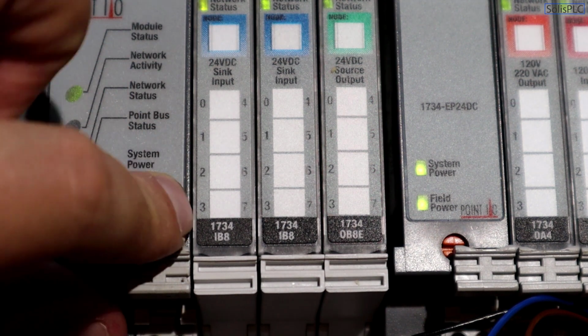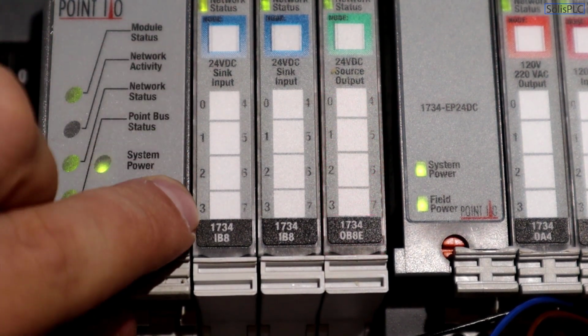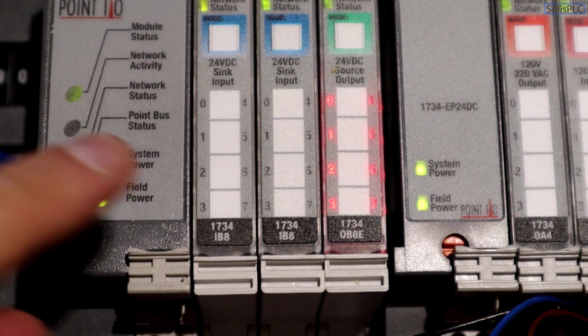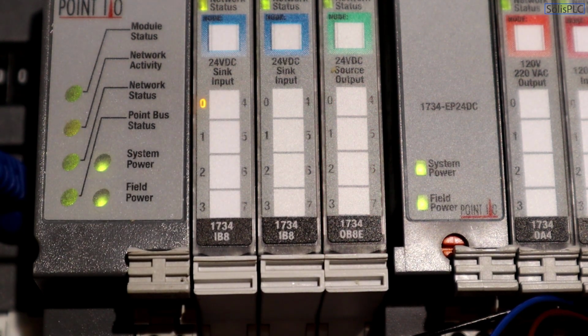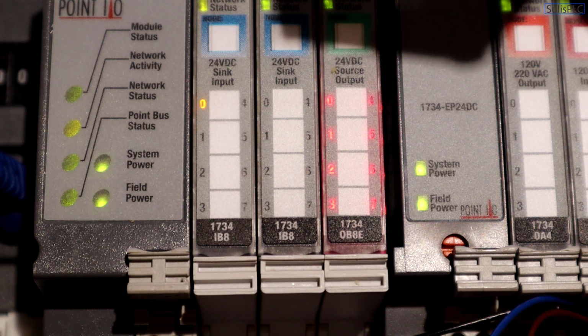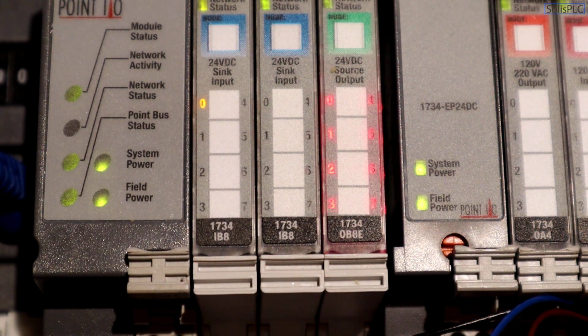So you'll notice that there's going to be an indicator for each single input. And when that input is on, then there's going to be that light that comes on. And this is the easiest way to troubleshoot in the field without having access to your PLC, that the sensor is essentially sending a signal and that the input is being triggered on the proper side. So if you're doing some maintenance, if you're doing maybe some new installation, then you can trigger the sensor through the means of just using your hand, and you can see which input is being triggered on the POINT I/O rack.